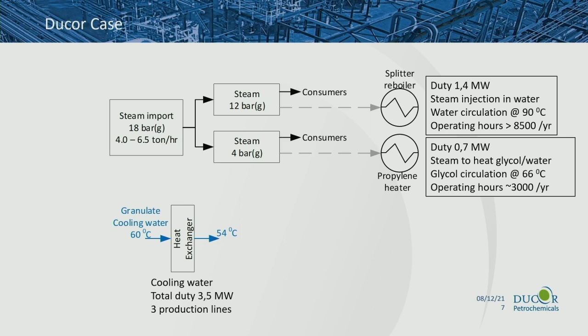But then the Ducor case. Some highlights: we have steam imports at 18 bar G, on average 5 tons an hour. Main consumers include a splitter reboiler with 1.4 megawatts duty, average steam flow over 2 tons an hour, where steam is injected into water to maintain 90 degrees Celsius in a water circulation loop. This was engineered and built 40 years ago; nowadays we would do it differently, but that's the current situation in our plant.